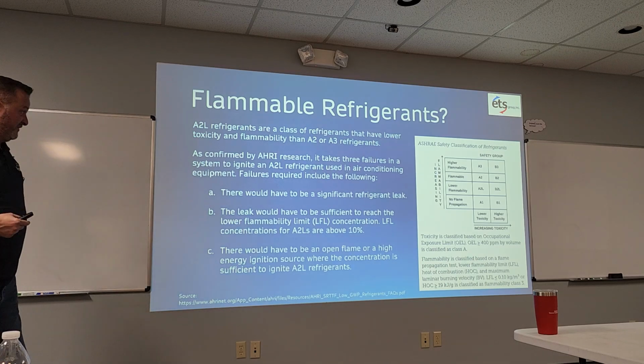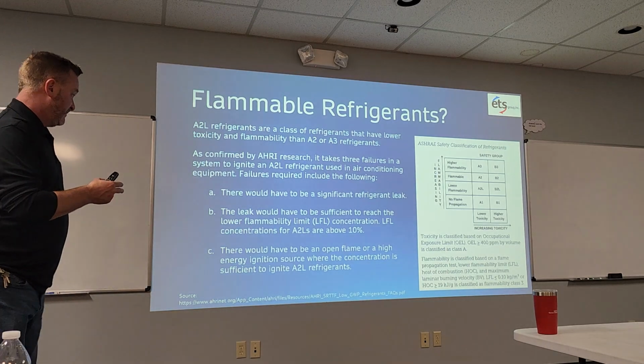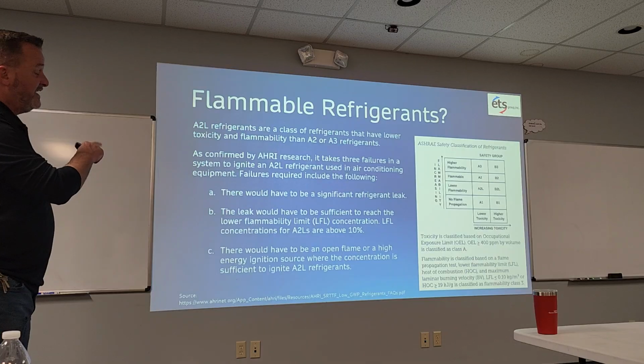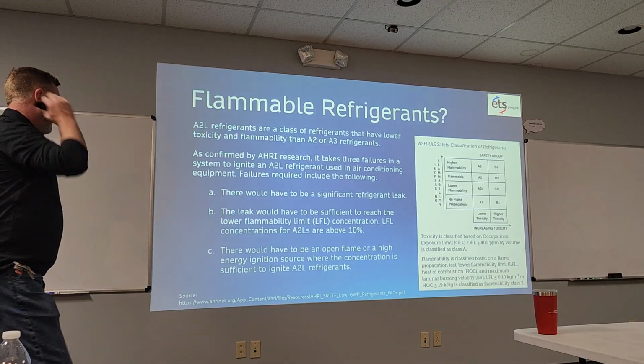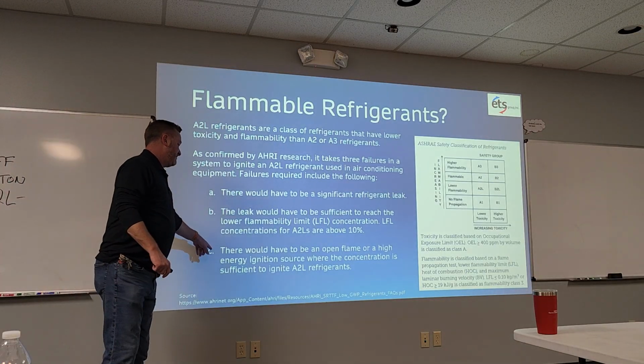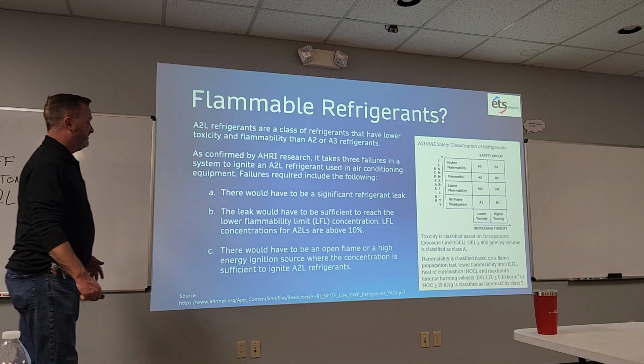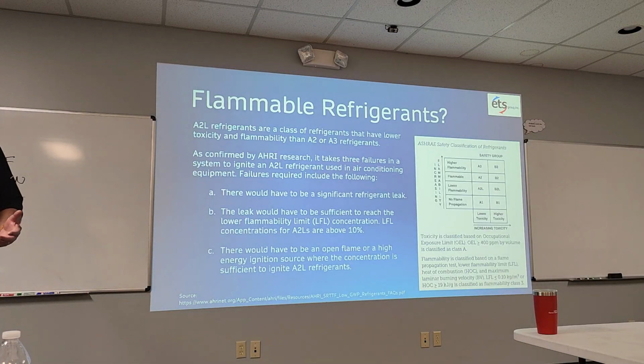So there'd have to be a significant refrigerant leak. The leak would have to be sufficient to reach the lower flammability limit, which for A2Ls is concentrations above 10%. And there would have to be an open flame or high energy ignition source where the concentration is sufficient to ignite the refrigerant.